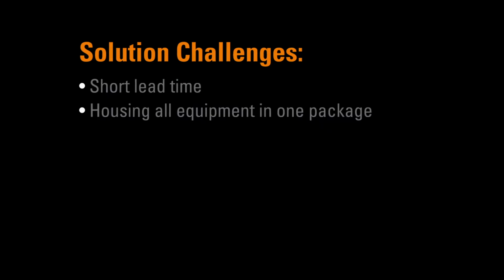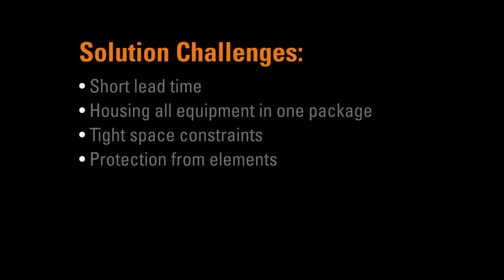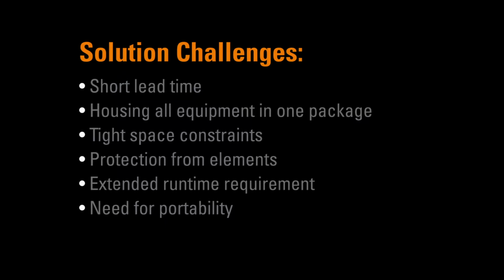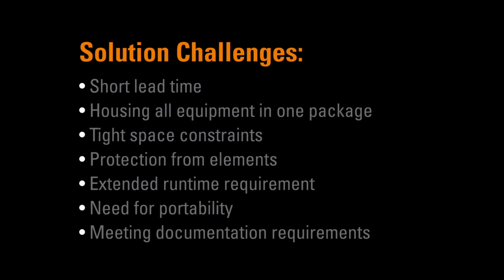The challenges we faced in creating the solution included the end customer's critically short lead time, housing the UPS, battery modules, maintenance bypass, transformer, and power distribution in one package, minimizing the footprint to meet space constraints, protecting the internal equipment from dust and water, the requirement for extended runtime, the need to be portable, providing complete submittal and drawing packages meeting the end customer's compliance and document control requirements.